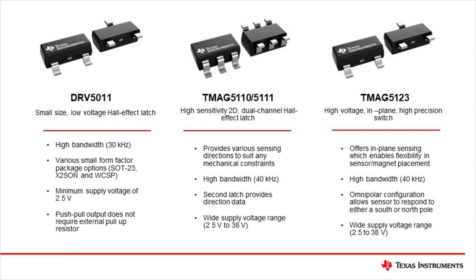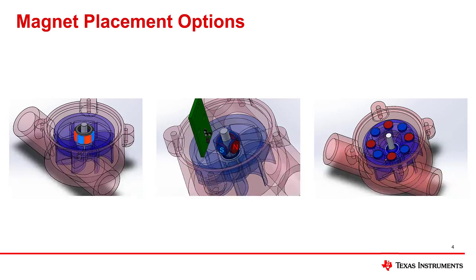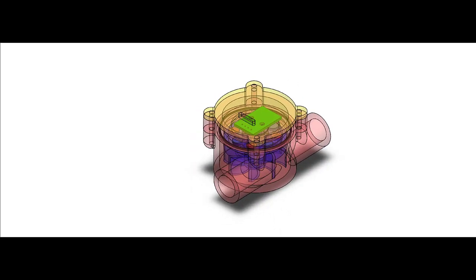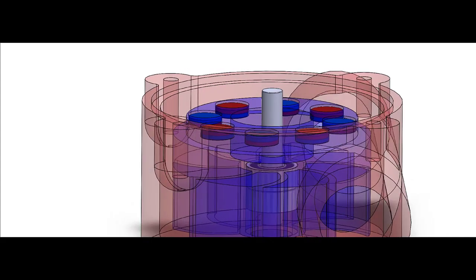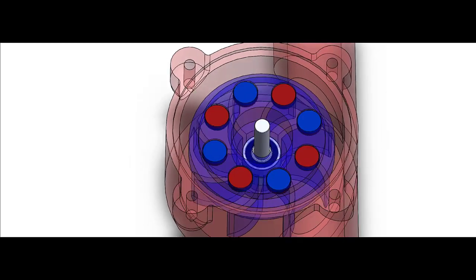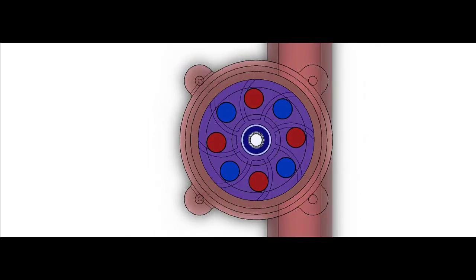If we have an impeller that is properly designed to meet our flow requirements, there are a couple of design specifications that need to be taken into consideration, such as magnet placement and sensor placement. For this demo, we have decided to use axially split disc magnets. The magnets will rotate along with the impeller housing and are fitted in an alternating pattern based on the field's polarity. This results in similar behavior as if using a ring magnet with multiple poles.